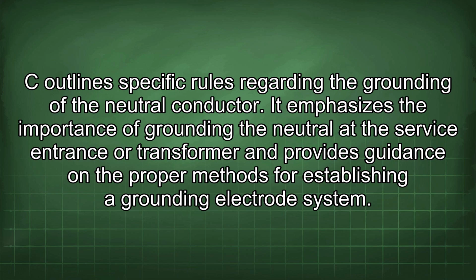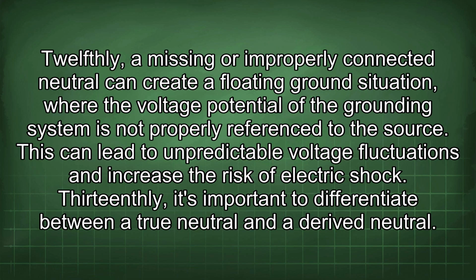It emphasizes the importance of grounding the neutral at the service entrance or transformer and provides guidance on the proper methods for establishing a grounding electrode system. 12thly, a missing or improperly connected neutral can create a floating ground situation where the voltage potential of the grounding system is not properly referenced to the source. This can lead to unpredictable voltage fluctuations and increase the risk of electric shock.